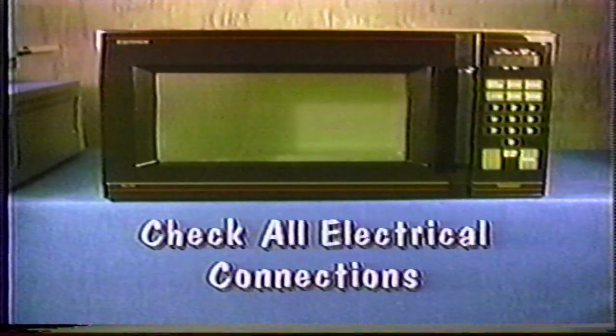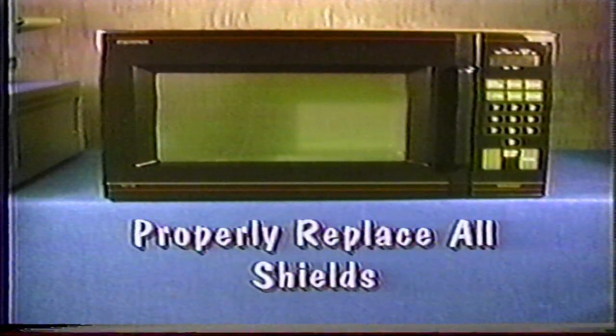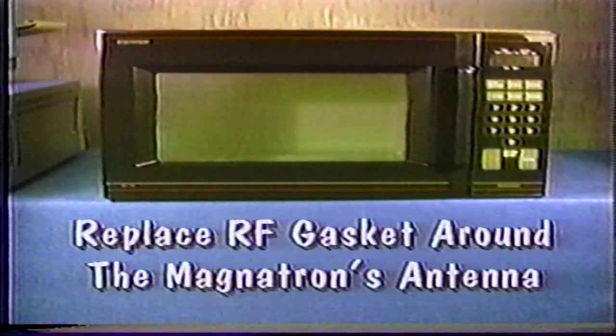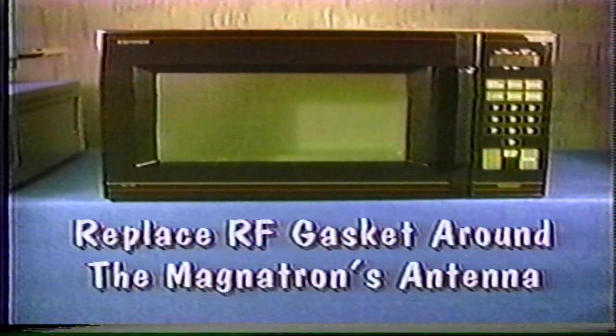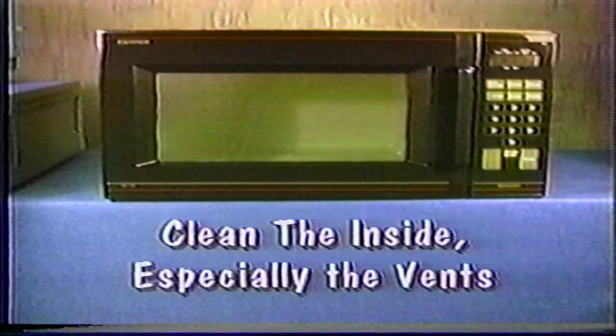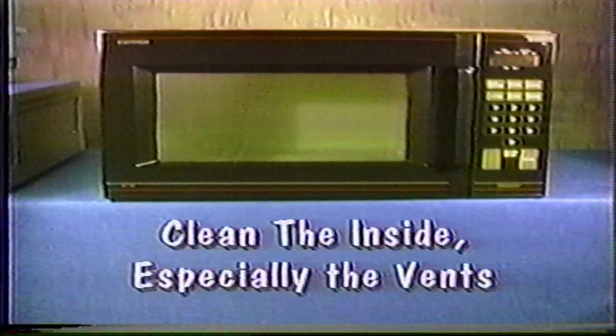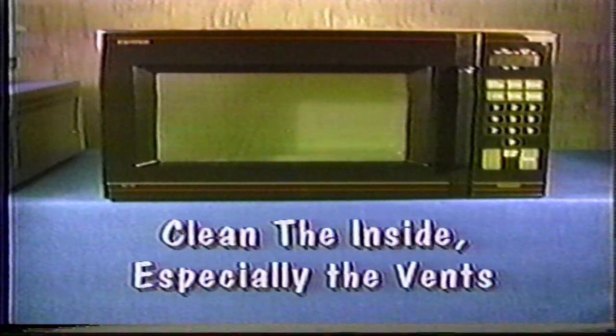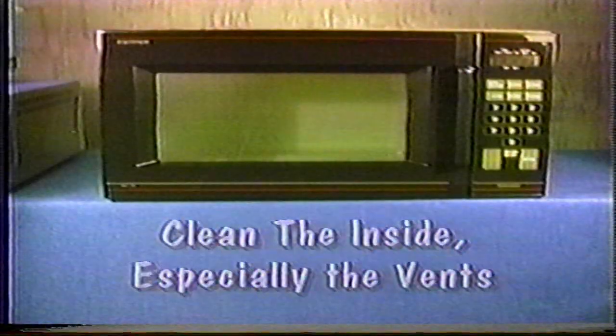Remember, you are dealing with lethal voltages. If you had to move or relocate any protective shields, put them back properly. If you removed or replaced the magnetron, make certain that you replace the RF gasket around the antenna. Before replacing the cover, clean out the inside thoroughly of any food materials, especially grease, which is, of course, flammable. Also, check all vents for blockage and food collection. Make sure that there are no extra parts or screws left over. This could cause a malfunction or allow excessive microwave energy to be emitted.